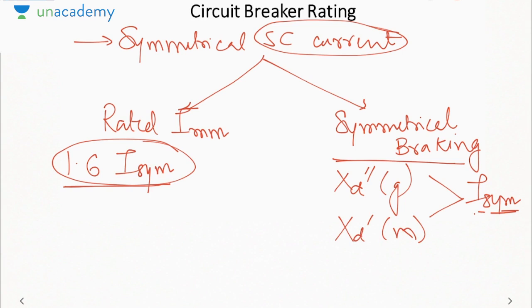Now, whenever you are opening the circuit breaker, the current which the circuit breaker is encountering is called the symmetrical breaking current. The later you open the circuit breaker, the lesser the current it has to open. The earlier you open it, the higher the current will be. Why? Because as time passes, the DC offset current decays down to 0. In steady state, the DC offset current is 0. In subtransient, the DC offset current is highest. So the factor that you have to multiply with the symmetrical current depends on the speed of the circuit breaker, that is, when you are opening the circuit breaker. If you are opening it early, you will multiply it by a high factor. If you are opening it late, you will multiply it by a low factor. So let us see what factor we have to multiply.